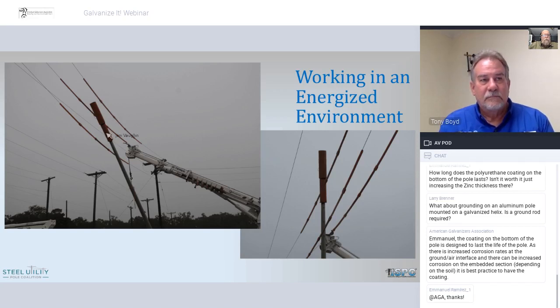But it's important also to know that a lot of linemen will forego the use of plastics because in their experience, they go out and set hundreds of poles just like this, and they grab the pole with the pole grabbers. They have very good control over the pole, and it never comes in contact. And I see this all the time with setting poles without using plastics. We shouldn't be doing that. You absolutely can't do that with steel poles.